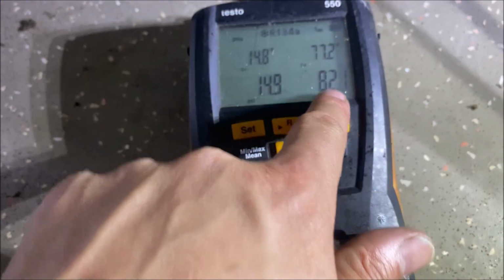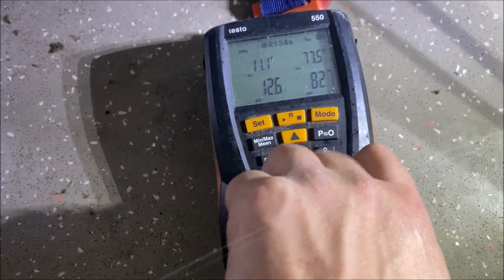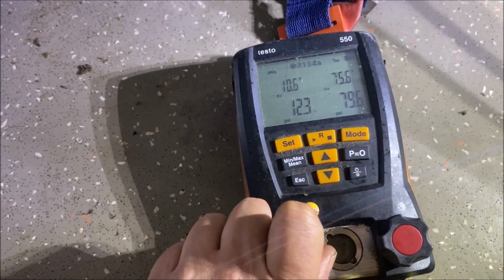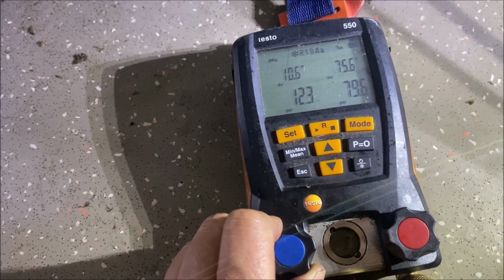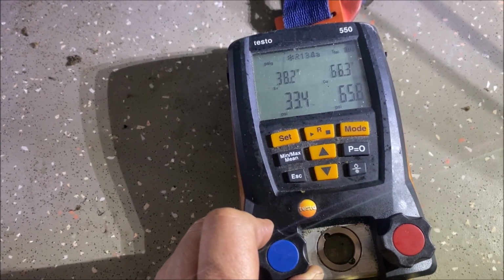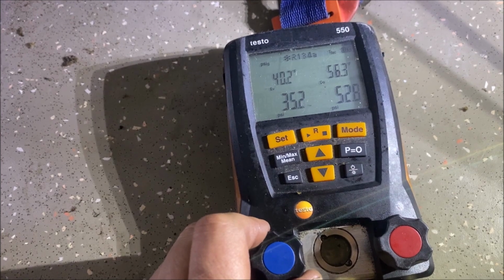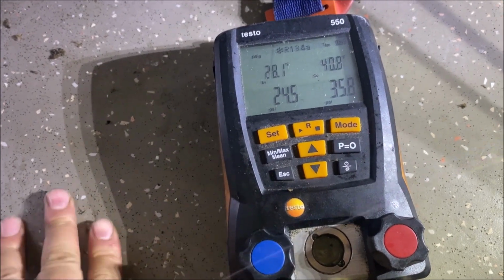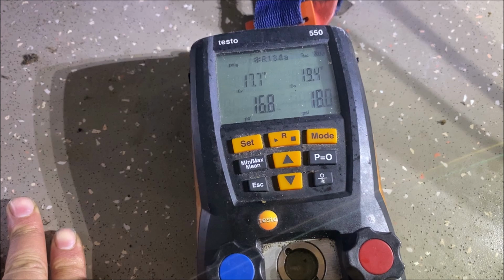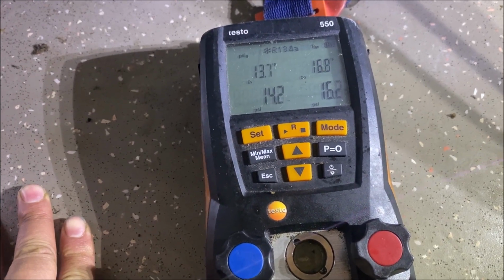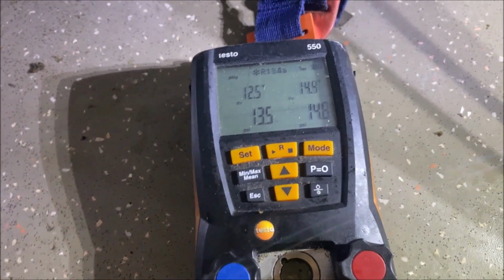So one last thing I want to show is you have refrigerant in your hoses here. Okay, so I remove my high side hose. I'm gonna crack it open and I'm gonna slowly throttle it into the low side. Okay, keep in mind, this is liquid. We don't like liquid in the low side, especially going to the compressor. So we're gonna slowly throttle it in and that's gonna ensure that we're not gonna lose our critical charge. And our unit cycled off, we're at 36 Fahrenheit, we're all good.